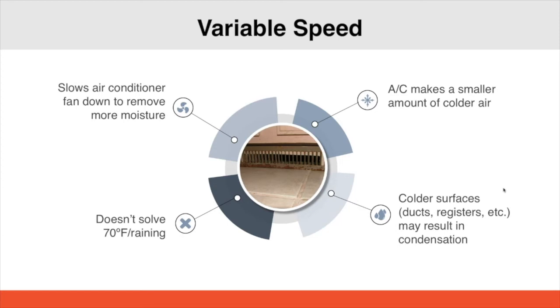And again, it makes a smaller amount of colder air, so we have to be careful that we're not getting condensation anywhere in our ductwork or registers. We still need to be delivering air to the farthest points of where the ductwork ends. So we still have to get to that comfort as well. We can't just be overcooling to dehumidify and not getting our air to the farthest points of the house. And again, it doesn't solve 70 and raining.